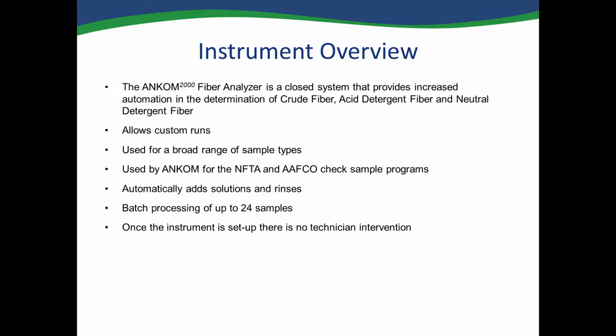The instrument is used for a broad range of sample types. The ANKOM A2000 is also used for the NFTA and AAFCO check sample programs. The A2000 automatically adds solutions and rinses and requires no technician during the run. The instrument does batch processing, allowing you to run 1 to 24 samples per run.